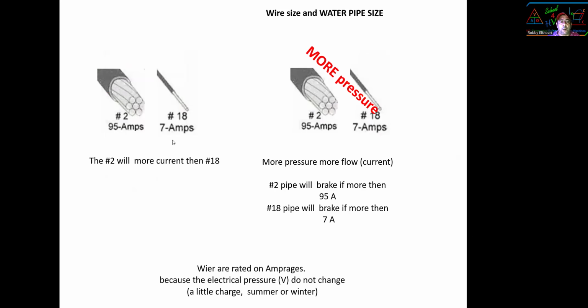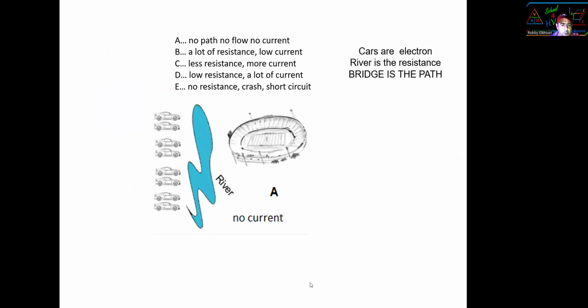Same thing with the electrical, people. The size of the wire has nothing to do with the voltage in it, the pressure. It has to do with the current it's moving. Okay, a number 2 wire will easily move way more electrons than a number 18 wire, 2 and 18. The more pressure, the more flow, of course. A number 2 wire will burn if the current is 95 amps. A number 18 will burn if the current goes more than 7 amps. Wires are rated on amperage because the electrical pressure, the voltage, doesn't change much. A little between summer and winter. You know, in summer, people use more air conditioning. I hope this makes sense. So now let's go back here to this first. I don't have the slide here.